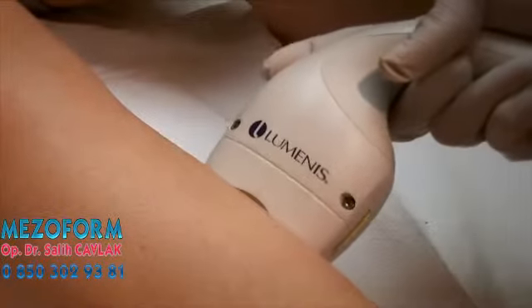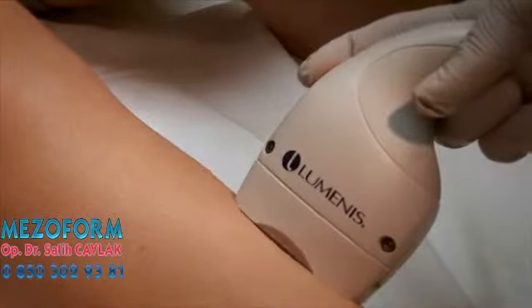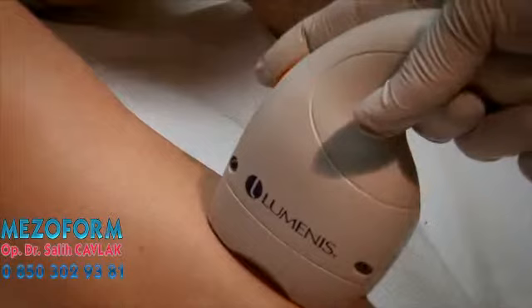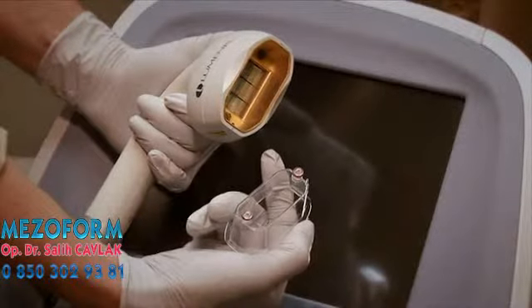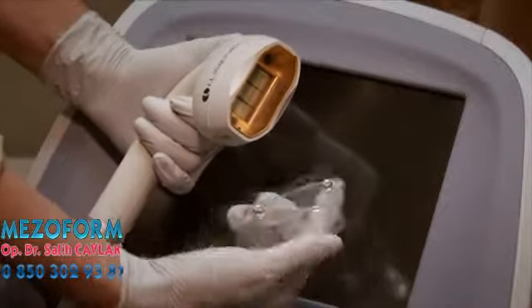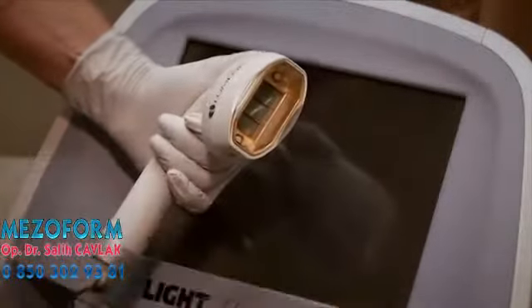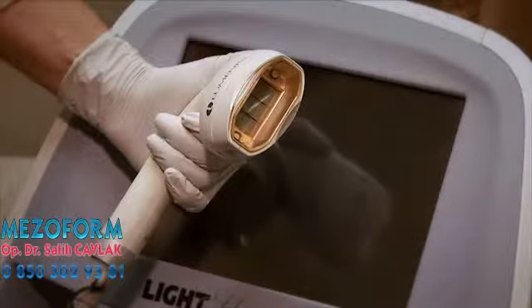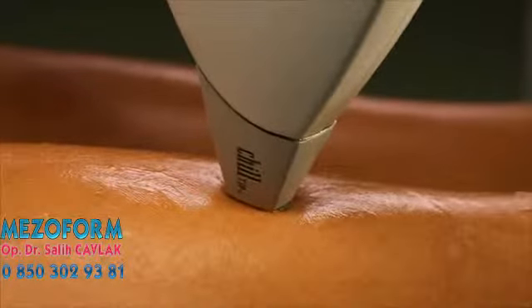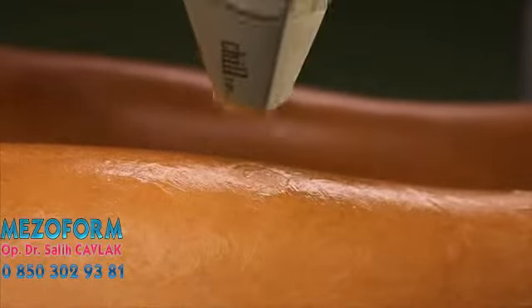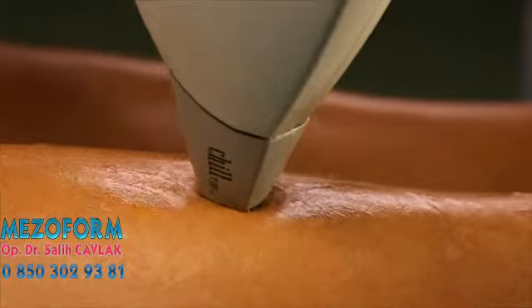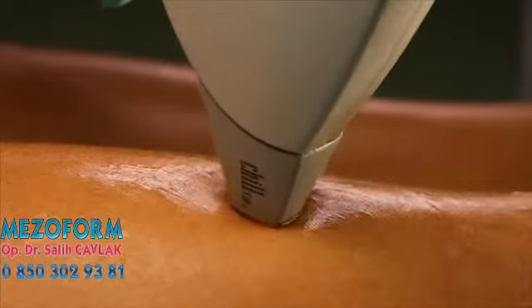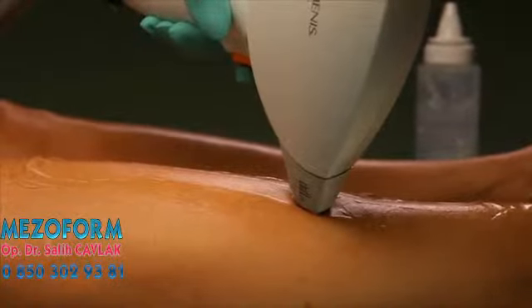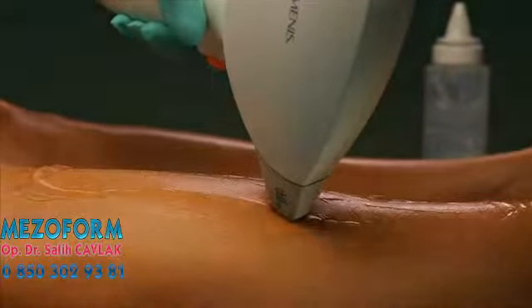Combining a larger aperture with vacuum assist technology affords the customer faster treatments by covering a larger area with each laser pulse. The HS handpiece utilizes a disposable insert which must be replaced with each patient, or during patient treatment if the tip becomes dirty or if the internal filters become clogged. The ET handpiece features a chilled sapphire tip that is pressed against the patient's skin during treatment and provides contact cooling to the patient's skin. By conductively cooling the skin, the chilled tip increases the tolerated fluence, provides partial anesthesia, and reduces temperature rise in the melanin-rich epidermis.